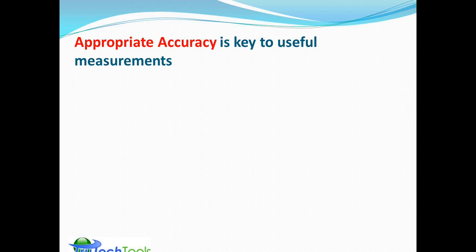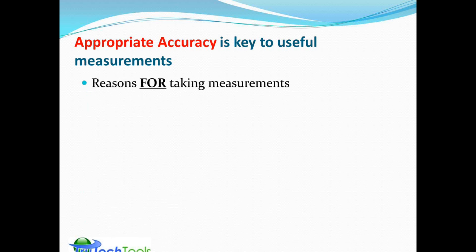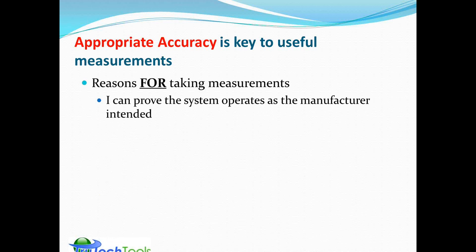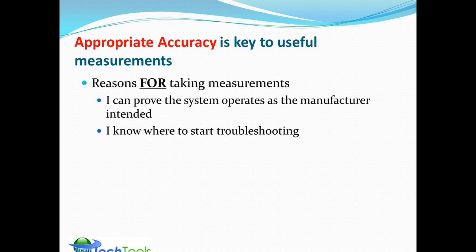There are various means and methods of measuring airflow, and appropriate accuracy is key to useful measurements. Reasons you might measure include: proving the system operates as the manufacturer intended, conducting a capacity test in BTUH or cooling tons, developing a troubleshooting baseline to detect duct leakage, coil bypass, dirty blower wheels, or open filter slots, and confirming that adjustments actually had an impact on the measurement.